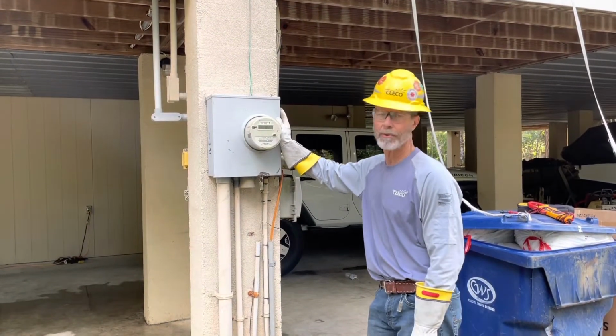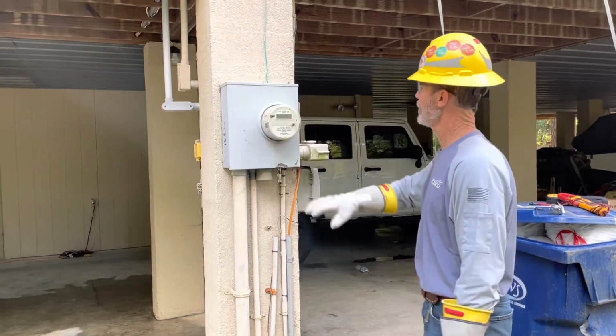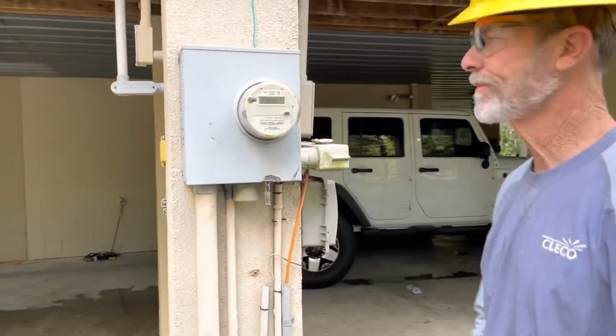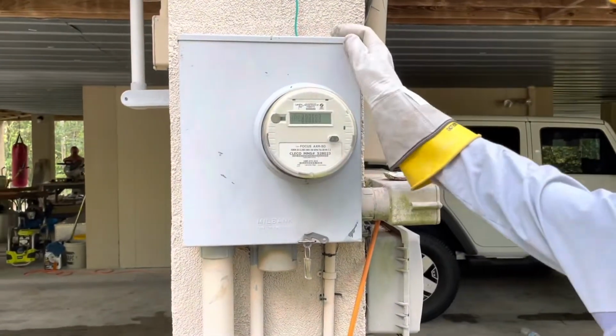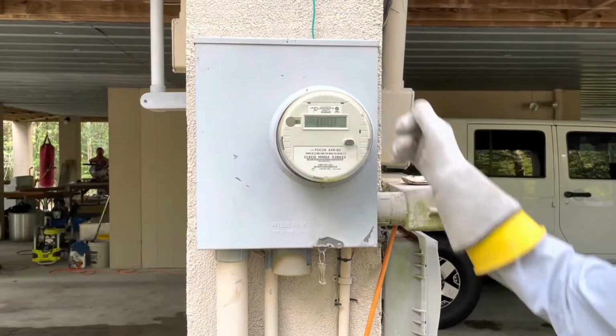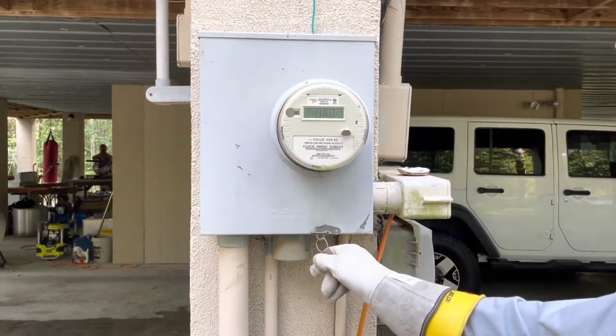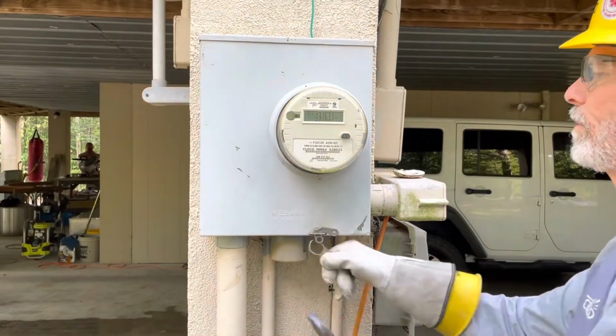The first thing you do when you walk up onto a site is you look at the condition of the meter pan. You make sure that the meter pan itself is connected good to the building and the meter's sealed. So we're gonna go ahead and open the meter pan up.